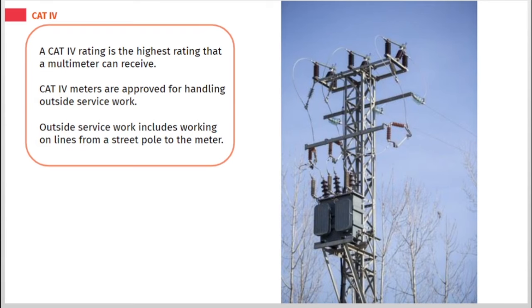A CAT 4 rating is the highest rating that a multimeter can receive. CAT 4 meters are approved for handling outside service work. Outside service work includes working on lines from a street pole to the meter.